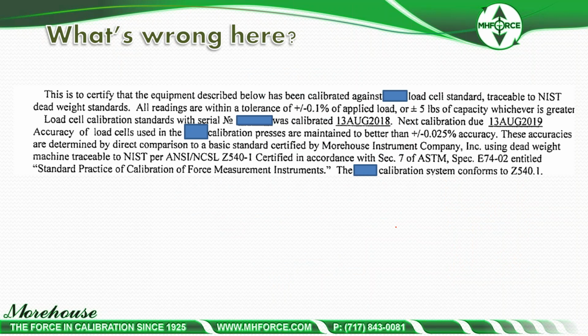This one, great. This is our company. Morehouse gets identified. We don't even do a calibration for this company. This is poor. This is to certify that it has been calibrated against a load cell, traceable to NIST, dead weight standards. Great. So how far are they away from dead weight? All readings are within a tolerance of 0.1% of applied or 5 pounds, whichever is greater. Load cell calibration with calibrated, next calibration due. Accuracy of the load cells using the calibration presses are maintained at better than 0.025% accuracy. These are actually direct basic standards certified by Morehouse Instrument Company using dead weight machines trade.